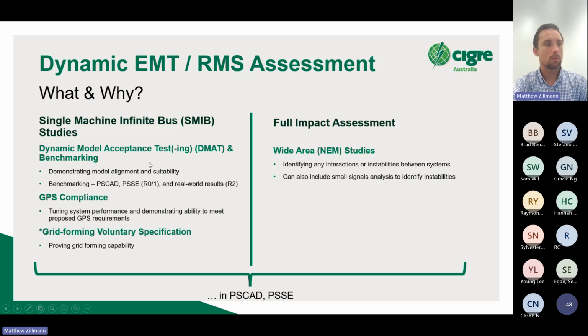That was developed with a view to having a standard set of tests people could benchmark themselves on. The benchmarking bit is that you'll have to provide PSCAD and PSSE models - two different software packages. PSCAD is EMT, PSSE is RMS, so pure time domain propagating waves versus everything assumed to be 50 hertz. You have to, as much as possible, demonstrate that they show similar performance - that they're in agreement, that when you run different tests and disturbances, they're aligned.